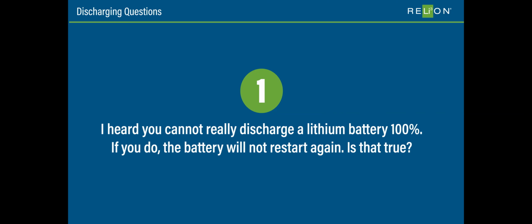Can you discharge a lithium battery to 100%, and will it harm it? Yes, you can discharge a lithium battery to 100%. Of course, the battery is depleted, the capacity is gone, and the BMS will do its function and disconnect at that point. That alone does not harm the battery. What does happen is, as long as you're connected to the equipment with a load present and the circuit stays physically connected, the BMS will remain disconnected and you won't have battery power. You actually have to physically disconnect the battery for it to recover or reconnect - some people call this 'restart'.